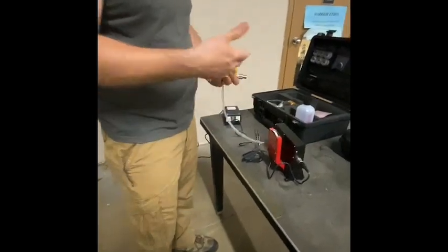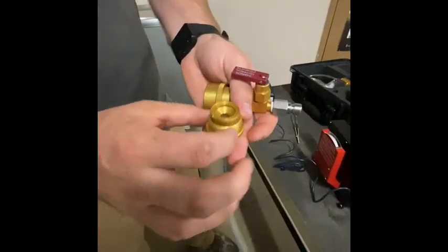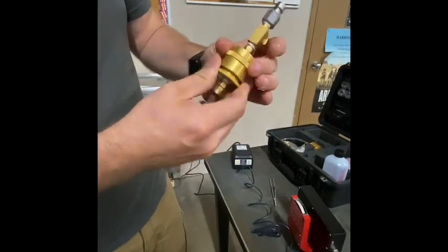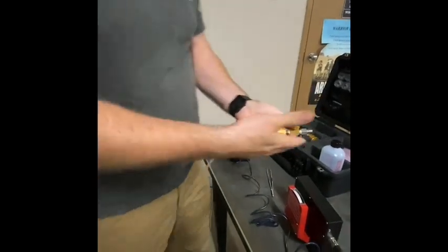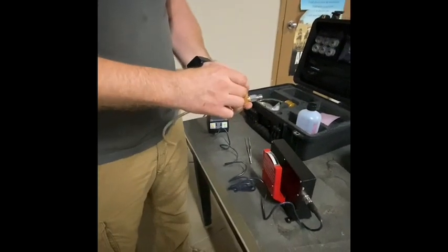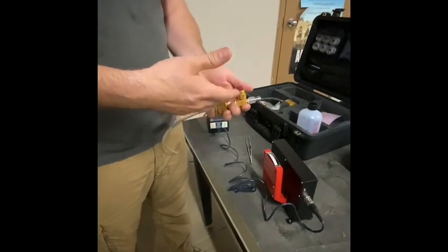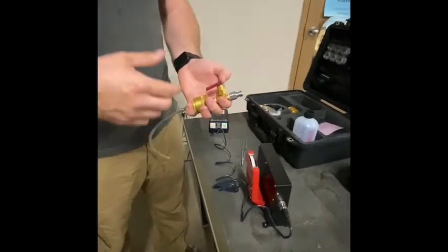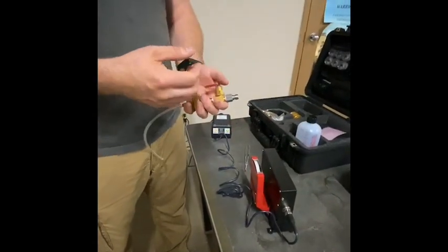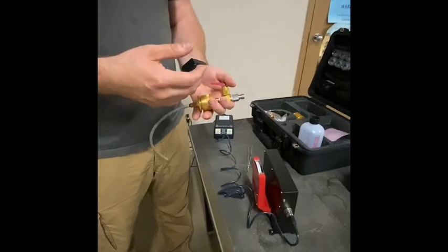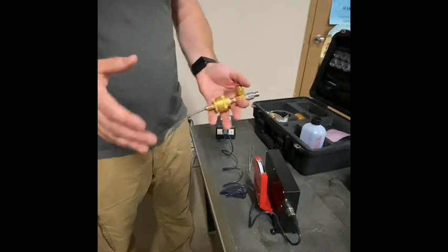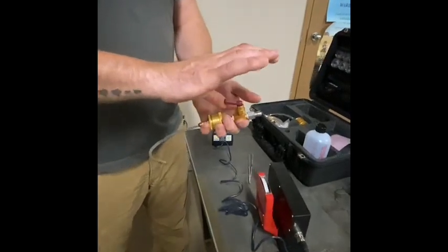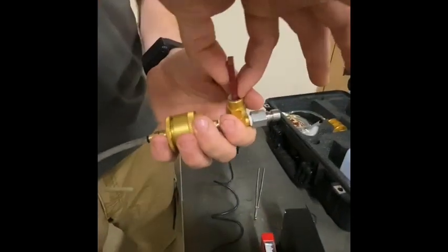So using the tweezers, you put the pad in sunny side up. Put it into the fuel testing device. Hook this all up to the fuel testing port. Make sure there's fuel flow to this. You want to use fuel that is running. So you would have your pump running. Whatever, if you're using your testing off a pump, testing whatever. You want the pump going, you want the fuel to be flowing. Open up the test port, open this up.